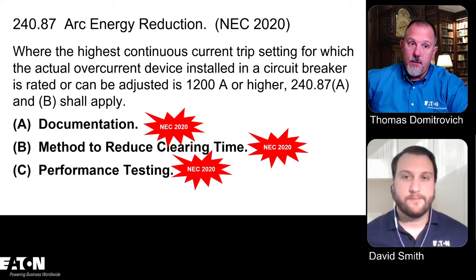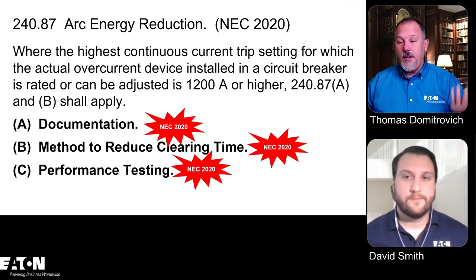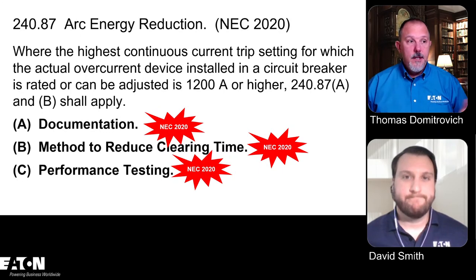And all that jazz. So your voltages are going to be all over the place, you know, in the voltage signatures. But yeah, for the most part, if you have a 480 volt system, it's a 480 volt system. And it's the impedance of the arc where the current is flowing and what that does to the current and all the harmonics on the voltage. So your voltage will fluctuate within the sine wave. Right.